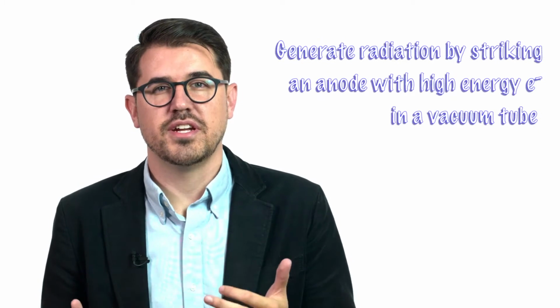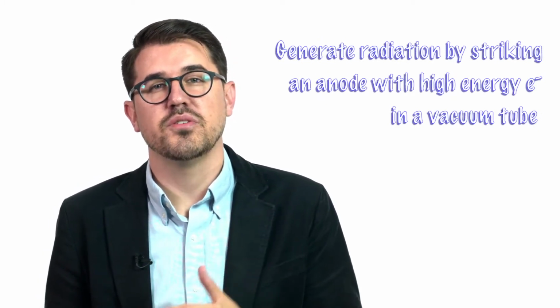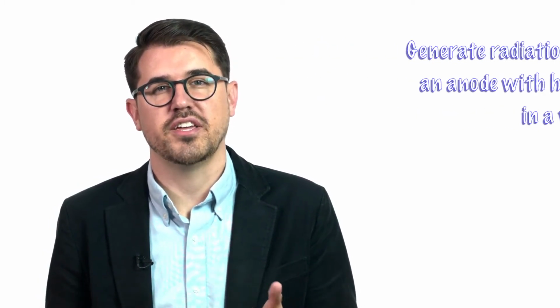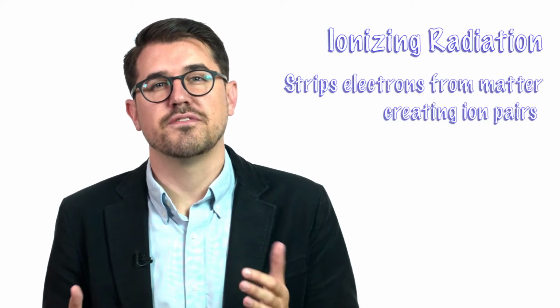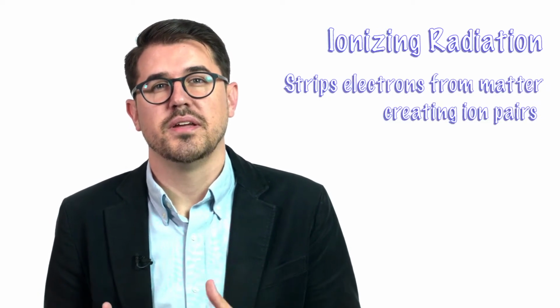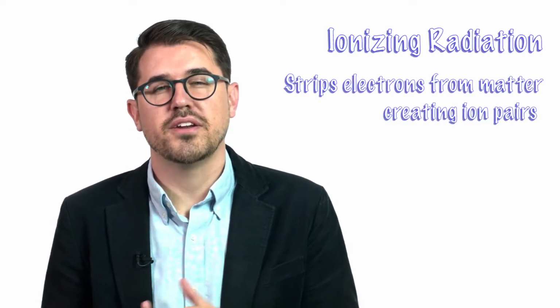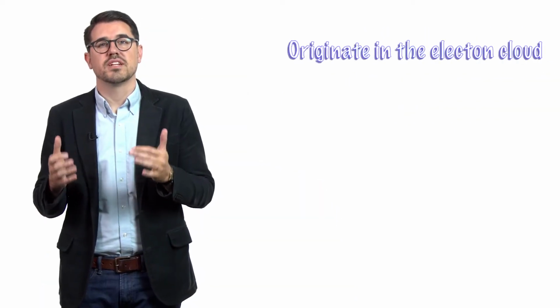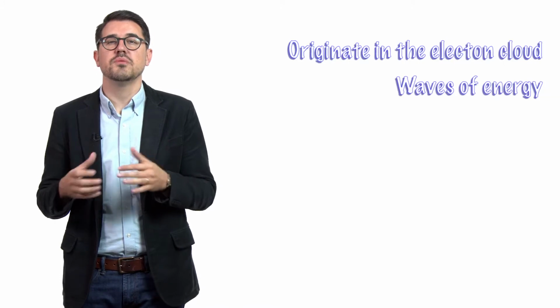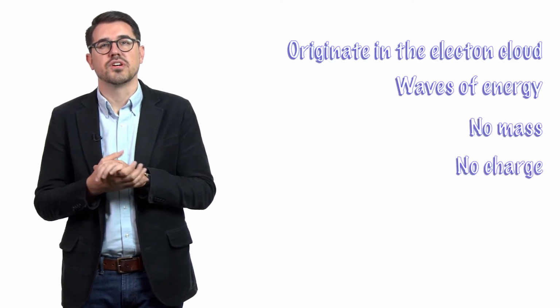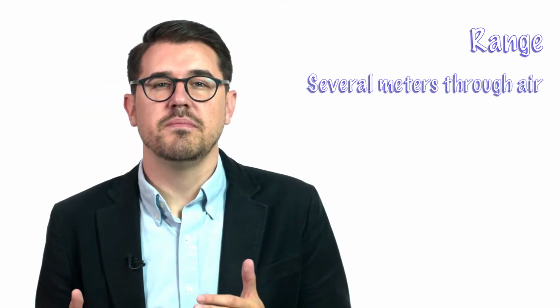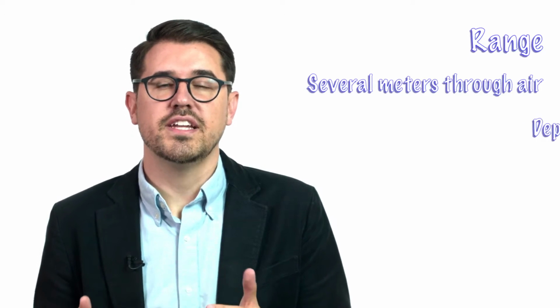X-ray devices generate radiation by striking an anode with high-energy electrons in a vacuum tube. X-rays are a form of ionizing radiation, meaning that they strip electrons from matter, creating ion pairs. X-rays originate from the electron cloud and are waves of energy with no mass and no electrical charge. Their range is many meters through the air, but can differ dependent on anode material.